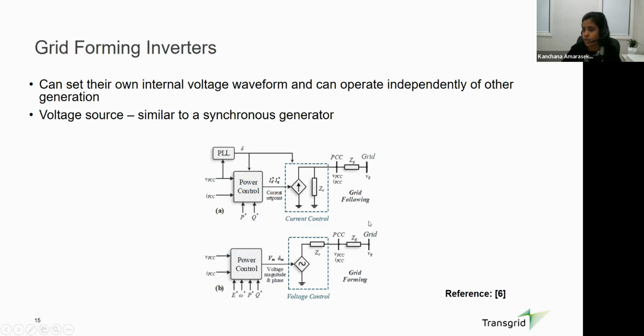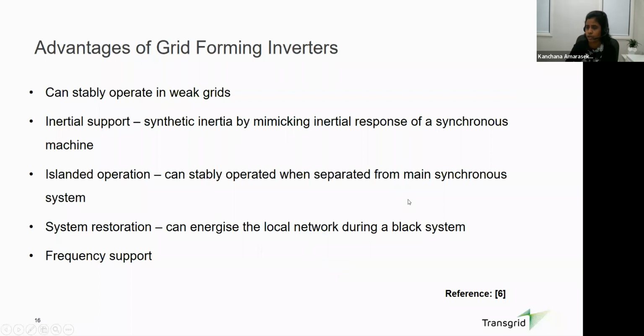So compared to a grid following inverter, it doesn't try to follow the grid voltage or rely on the PLL measurement. That is the key difference between grid following and grid forming inverters. Then what are the advantages of these grid forming inverters? As I mentioned, they can stably operate in weak grids. And the second advantage is there are ways to provide synthetic inertial support using these grid forming inverters.